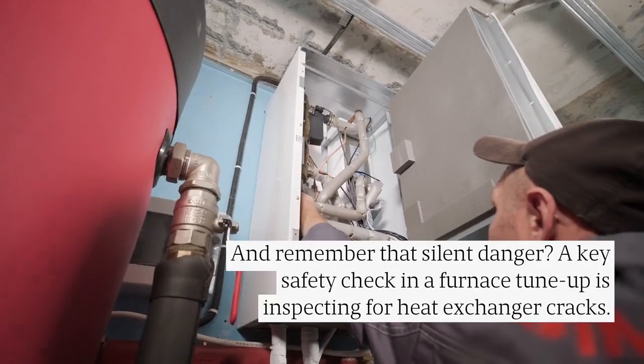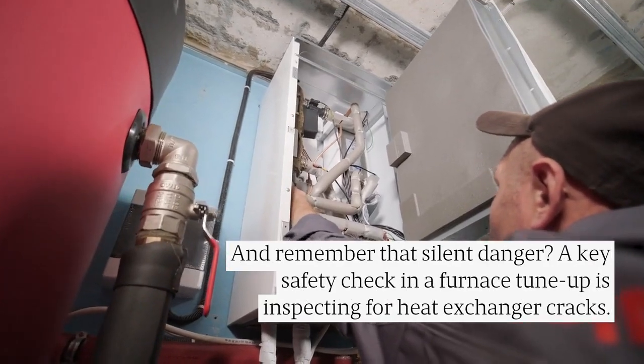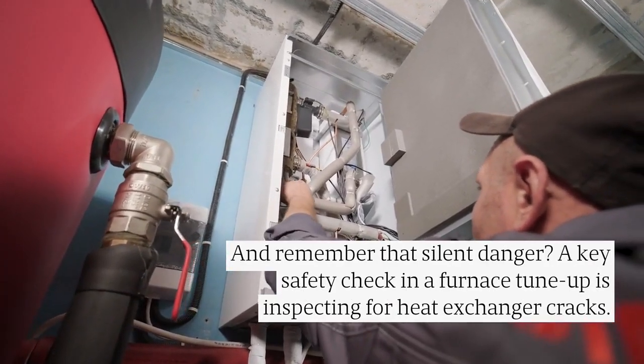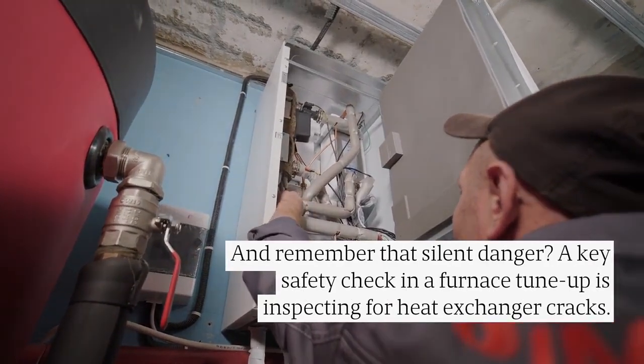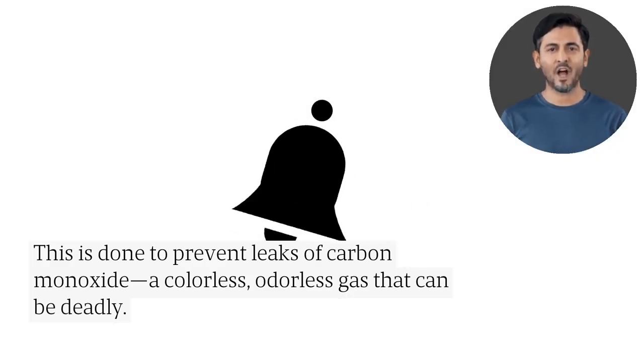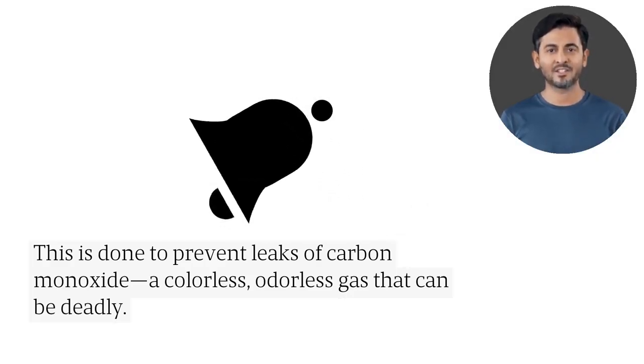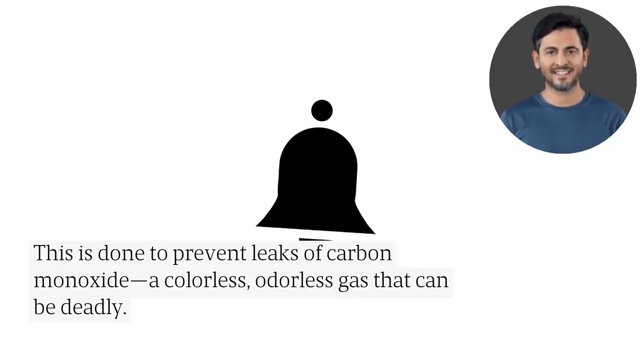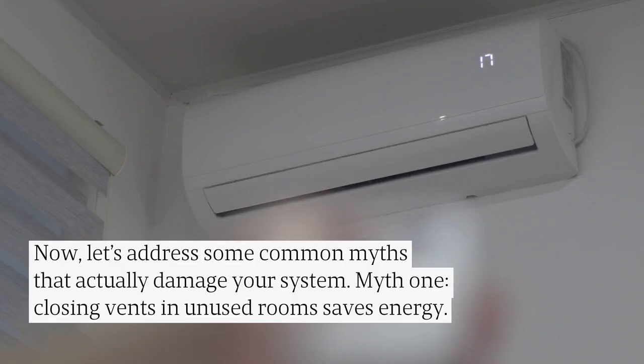And remember that silent danger. A key safety check in a furnace tune-up is inspecting for heat exchanger cracks. This is done to prevent leaks of carbon monoxide, a colorless, odorless gas that can be deadly. Now, let's address some common myths that actually damage your system.